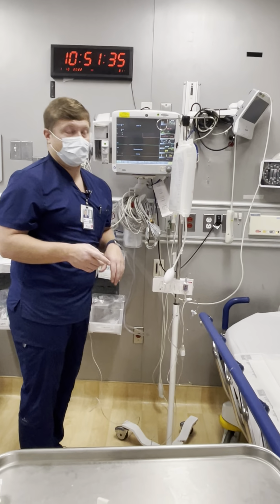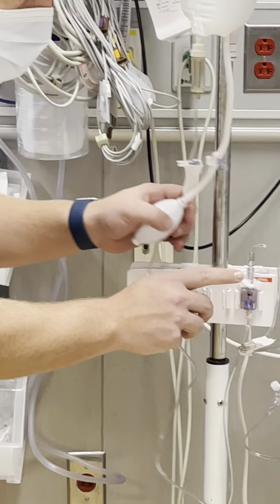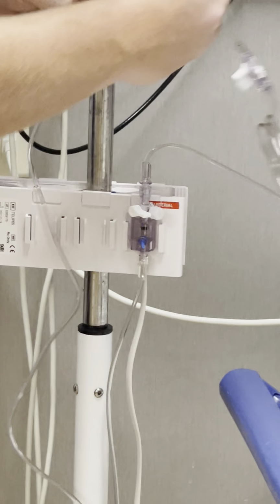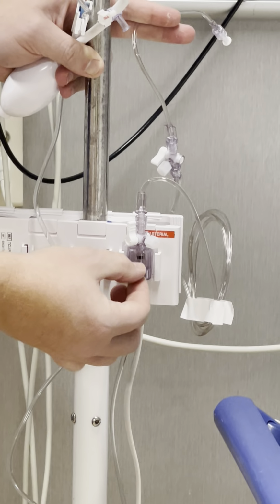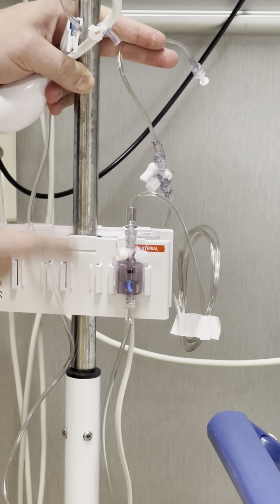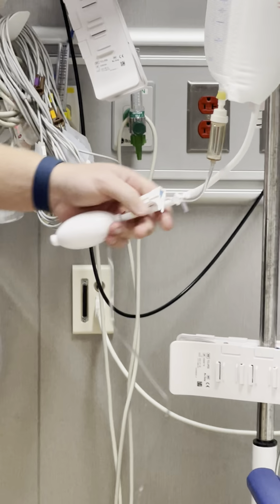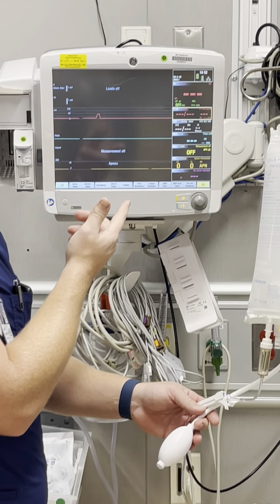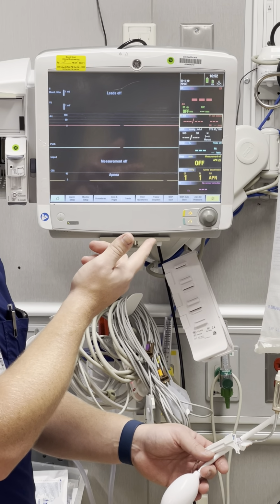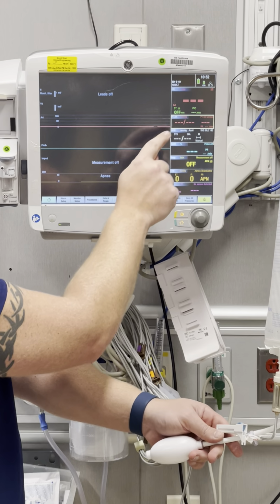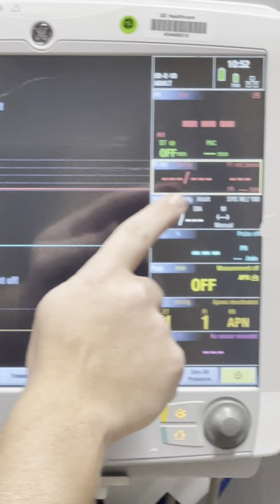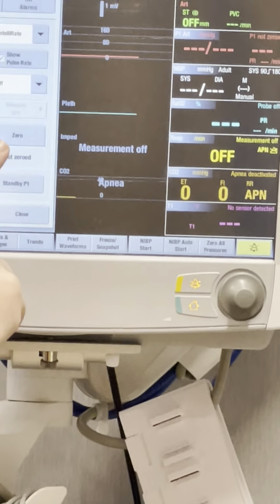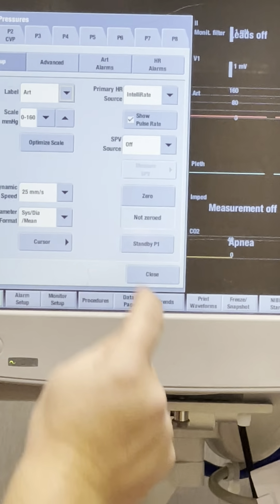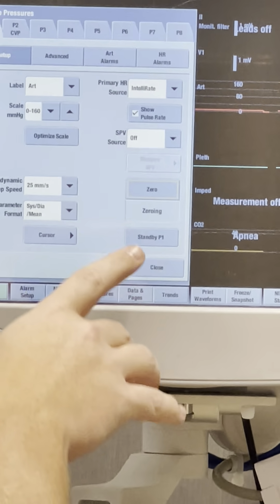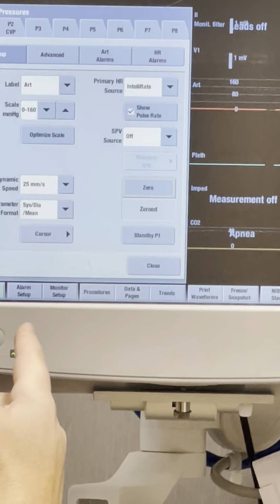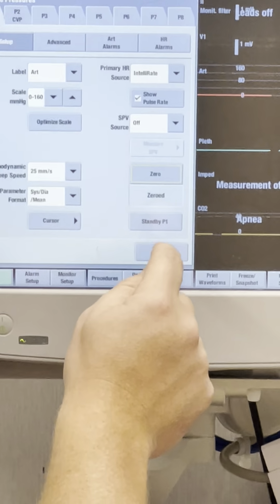zero this out, that's very important. We want to make sure we turn this transducer off to the patient. Remember, this is going over to the patient. We're going to turn it up. We're going to pull this tab one time and release. That allows all the pressure to come through. And then on the monitor itself, this is for the GE B650. The 850s are set up the same way, and so are the transport monitors of the 450s. You see right here, it will say P1 ART. If you click on it, there's an option to zero, and you can actually zero while it's turned off. That's very important. You just hit zero, it'll go to zeroing, and once it goes to zeroed, that's in past tense, then you know it's ready to be used on your patient.